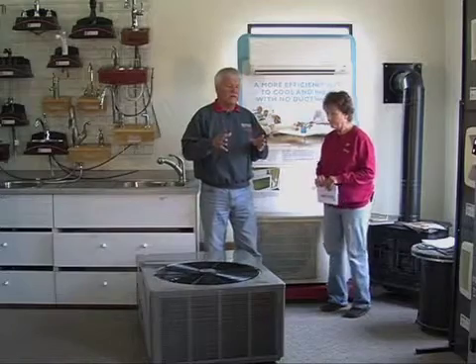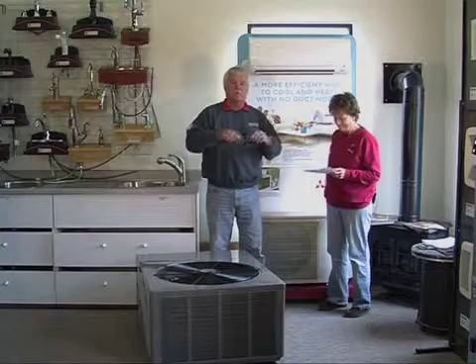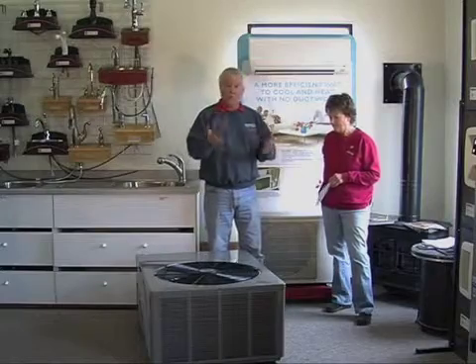Okay. When we talk about heating and now we're talking about air conditioning, in both those cases it's very, very important that we get the right size. And how we determine that is we come to your home and we measure the square footage of doors and windows and glass, and you can tell us how your home is insulated, and we can calculate the amount of BTUs we need for capacity.